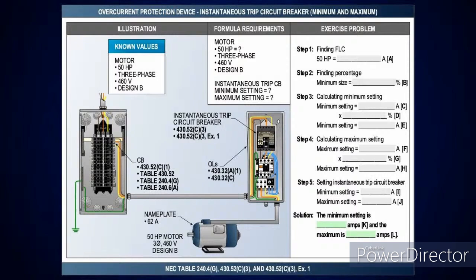Now, when you look at the 2023 version, it's very interesting because guess what they changed it to look like? It looks like I'm looking at 430.52(C)(1). And now they have an Exception 1, and it basically says the same thing: if it fails to start due to inrush current, guess what I can do? Automatically go up to the next size. And then they moved the 225% from the main code text. Now it's down in Exception 2 and allows you to go up to 225%, which would be your maximum. You know what 225% is?